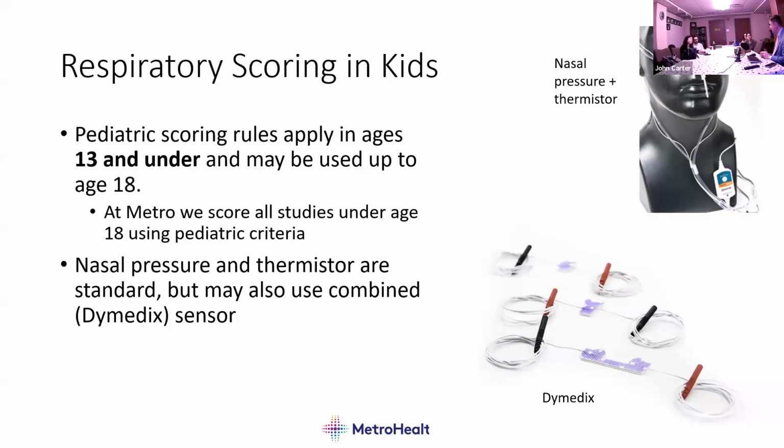Again, you may or may not know this yet, but if you're scoring an apnea, do you score it off the nasal pressure sensor or the thermistor sensor? Yeah, you mentioned it. Good. Do you know why? Again, I think you're going to hear more about this later, but the nasal pressure sensor signal changes as the square of the airflow.